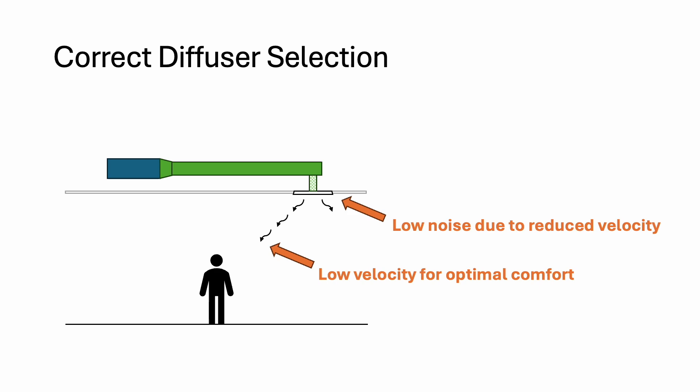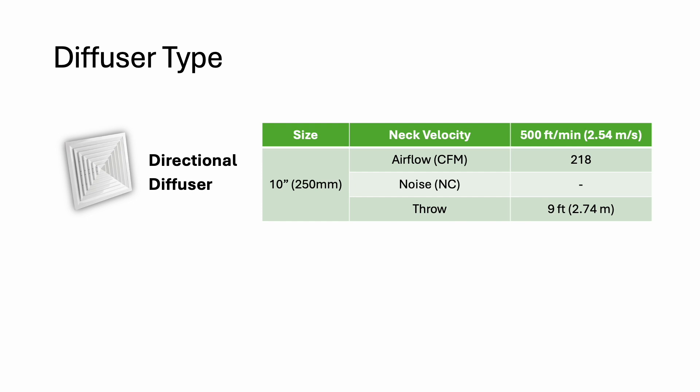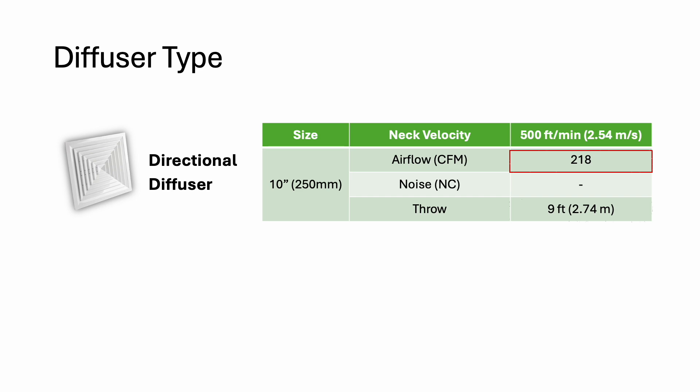Now, what does that have to do with the diffuser patterns? It turns out different patterns have different characteristics — meaning one pattern is good at controlling noise while another may be good at providing a longer throw. For example, when handling 200 CFM of airflow, a 10-inch directional diffuser has a throw distance of 9 feet.